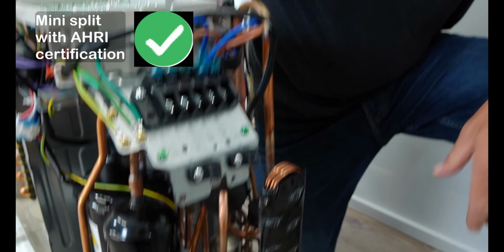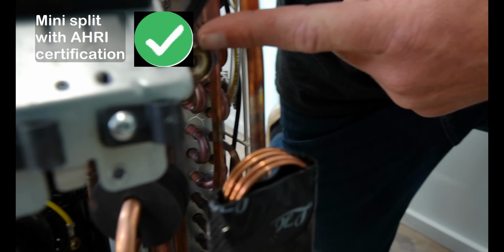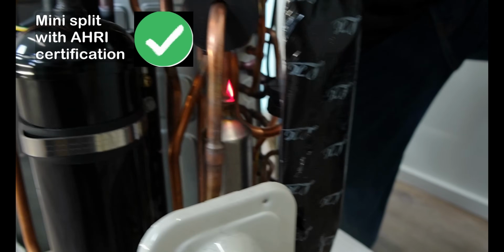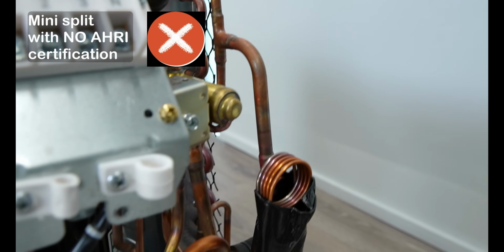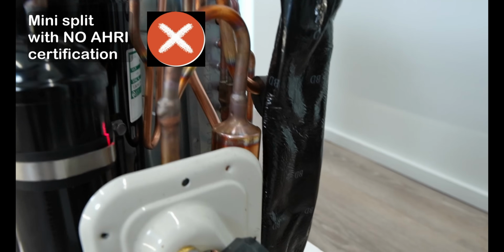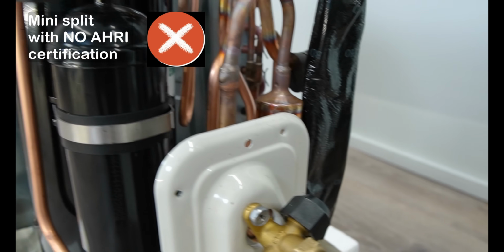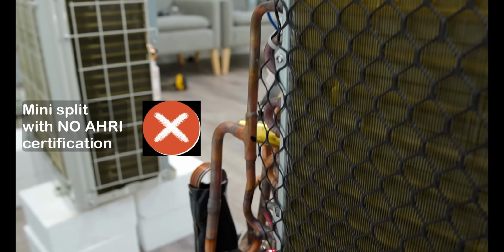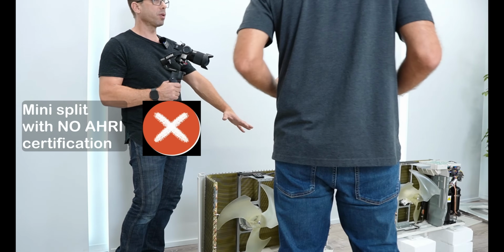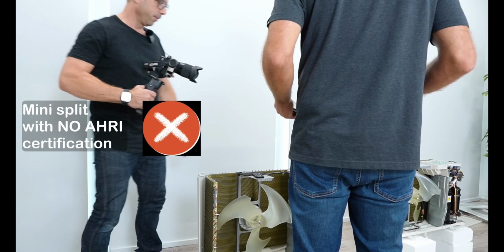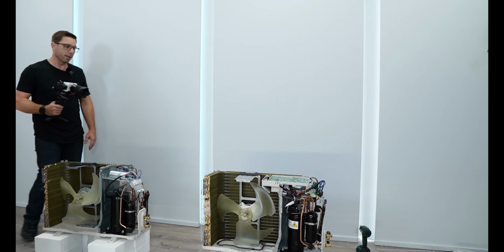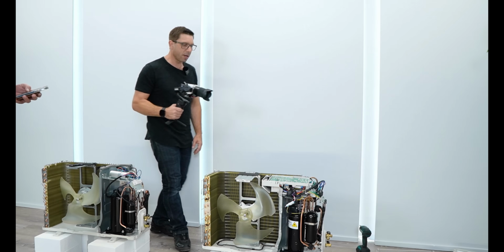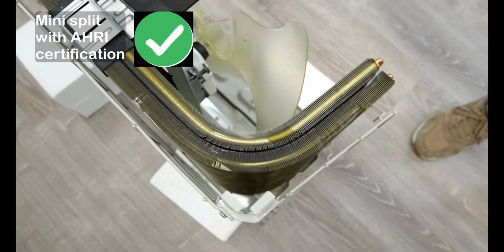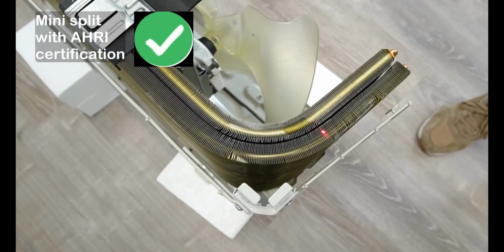So all the other components are pretty much the same. We've got a 4-way reversing valve, filter dryer, accumulator, same thing on this one. Standard stuff. And this one here has a temperature sensor right here. And this one does not. So this one has no idea what the ambient temperature is. No, it doesn't, because it's single stage. It's on or off, that's it. It's not an inverter. One major thing is the coil size on this is nearly double. You can see two rows, one, two. And this one has only one row.